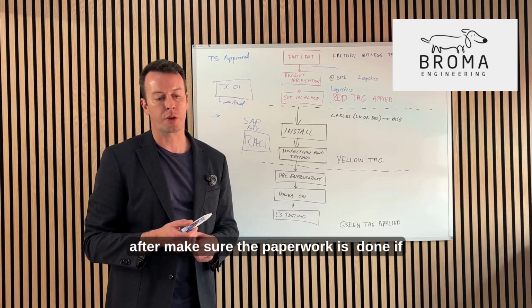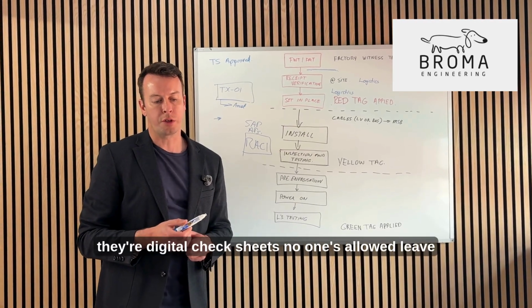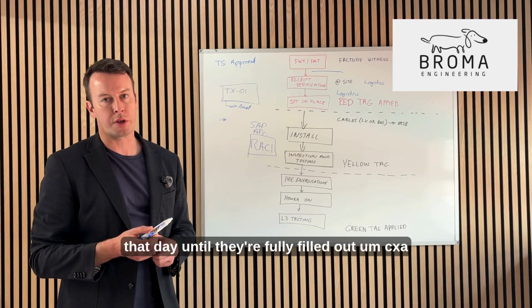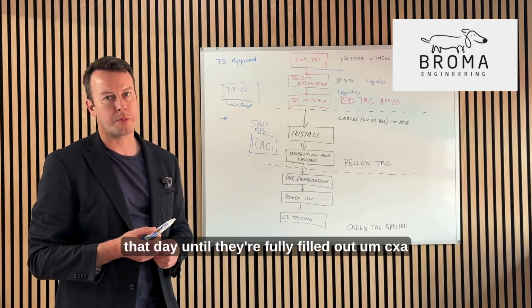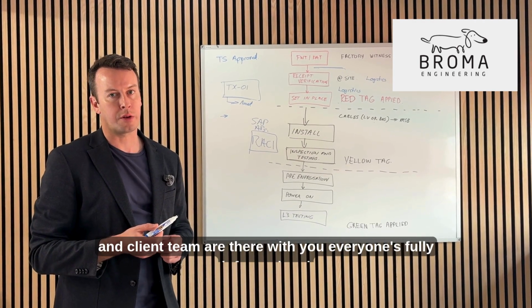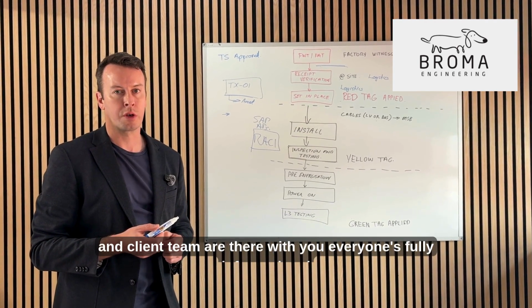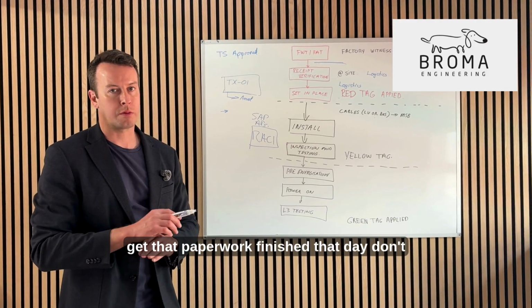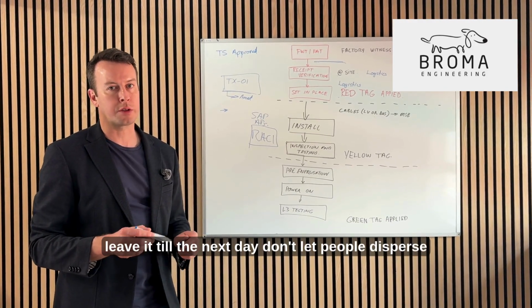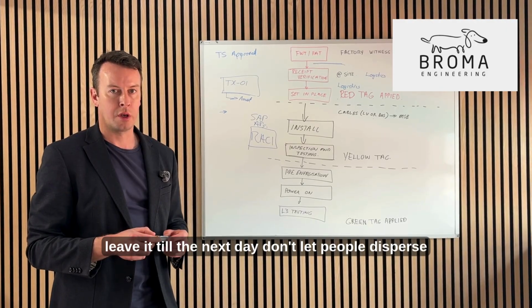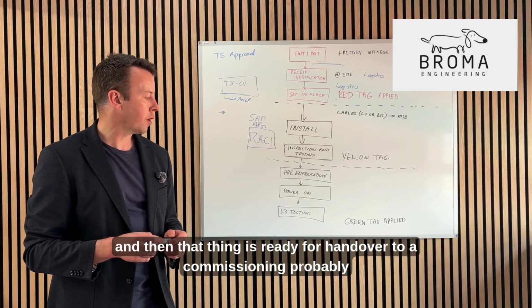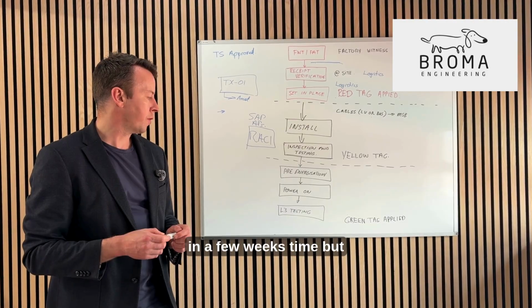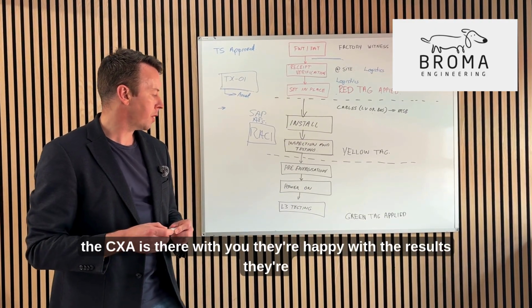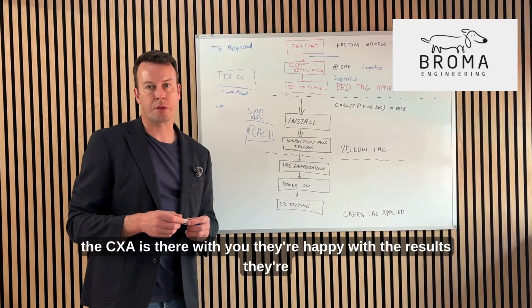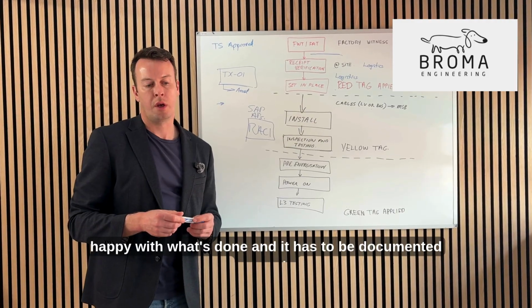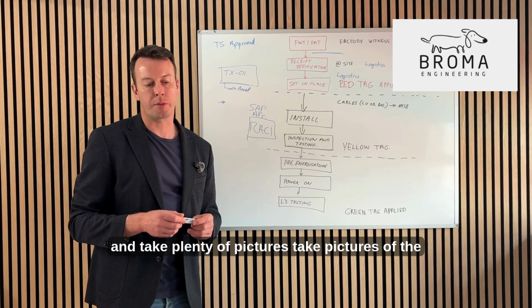That all needs to be tested pretty much after power goes onto it, so everyone knows exactly what they're supposed to do. It's in your power on plan that we're getting the bulk of the level 3 testing done just after. Make sure the paperwork is done. If they're digital check sheets, no one's allowed to leave that day till they're fully filled out. CXA and client team are there with you. Everyone's fully informed, and get that paperwork finished that day. Don't leave it till the next day. Don't let people disperse. And then that thing is ready for handover to commissioning, probably in a few weeks' time. But the CXA is there with you. They're happy with the results. They're happy with what's done, and it has to be documented properly. And take plenty of pictures.